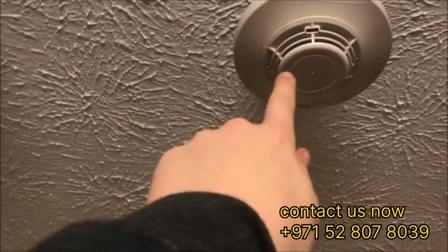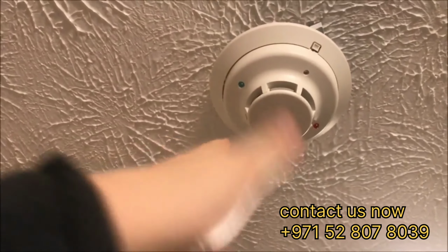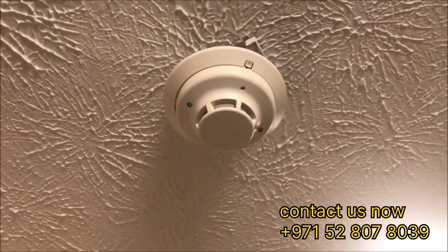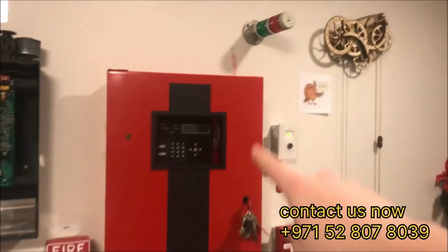And you can see that blinking light, that is the polling light. So that means every time it blinks, it's talking back to the fire alarm control panel. Same thing with all your smoke detectors. You can see they are blinking frequently as they're talking back to the panel, and a conventional smoke detector will only talk back whenever it's in alarm. They aren't going back and forth, it's just this to this. With these, the panel and the smoke detector are talking back and forth all the time.